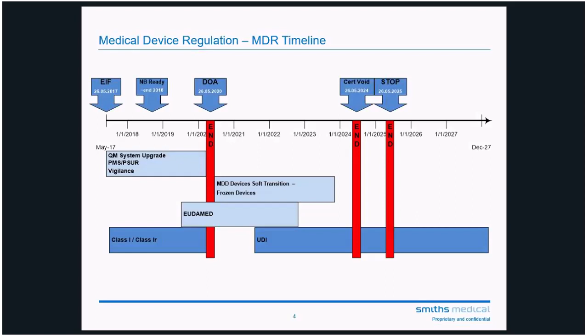So what you can see here is the outcome of the MDR's gap assessment, based on an Excel spreadsheet. It assessed all the relevant sections of the MDR, not just Annex 1, but also the other clauses that have labeling impact. For example, Article 13, Article 16, and Article 20 deliver separate requirements for that.